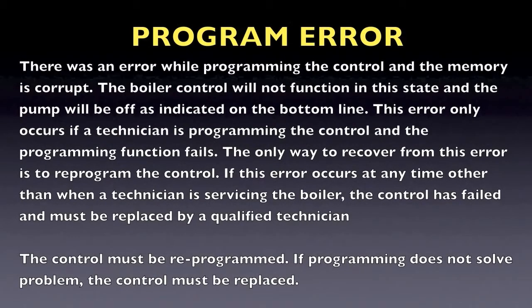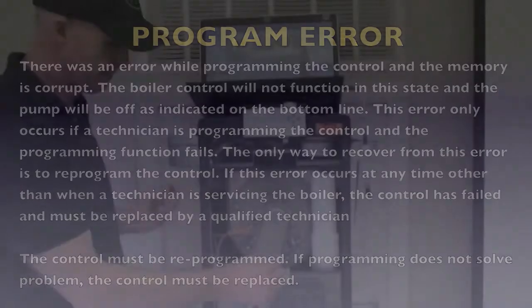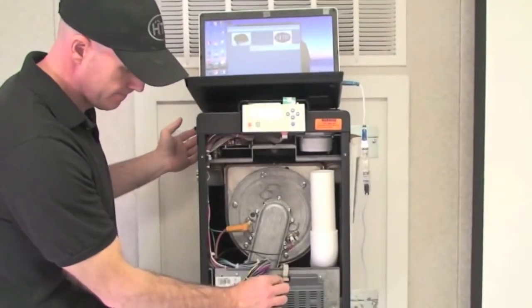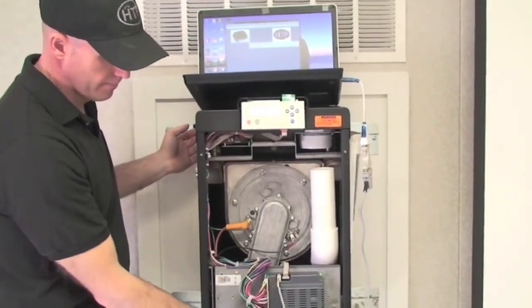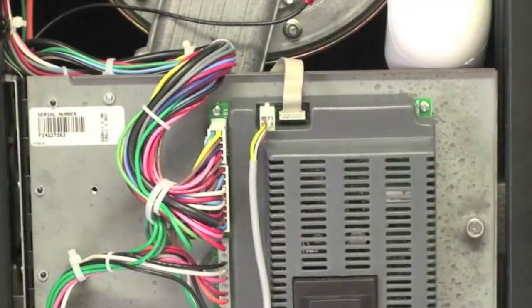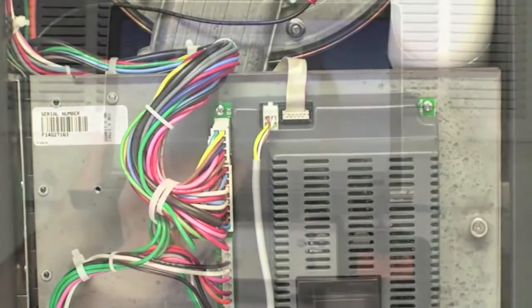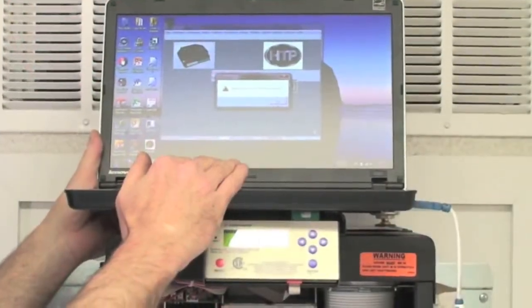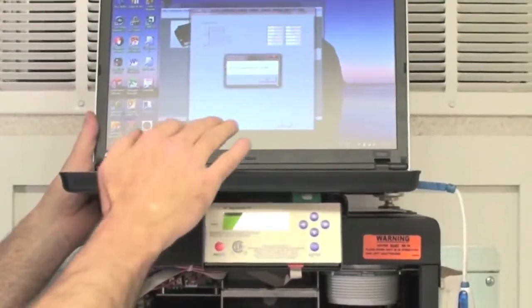The boiler control will not function in this state and the pump will be off as indicated on the bottom line. This error only occurs if the technician is programming the control and the programming function fails. The only way to recover from this error is to reprogram the control.